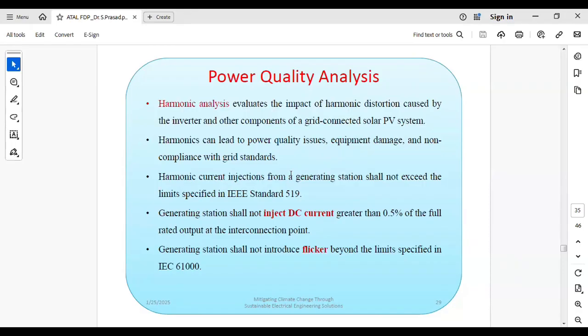If the current harmonics, voltage harmonics, total THD at the point of interconnection, you need to report how much it is, what the percentage is, and whether it lies within 5% or not. This is according to CEA regulations. Voltage harmonics also depend upon the voltage level at which you are injecting the power to the grid, 33 kV, 69 kV, 220 kV. According to that, the percentage of THD is decided and specified by the CEA regulations. You should be within that limit, then you will get the approval.